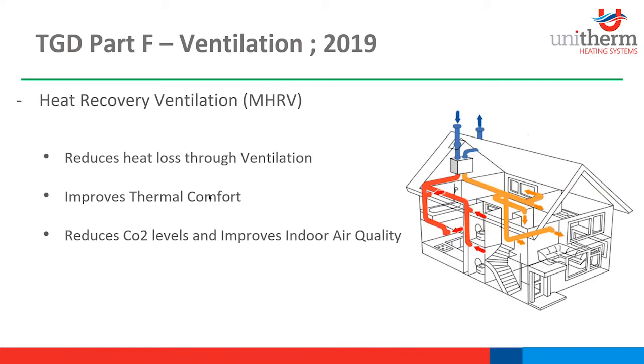So if you had warm air at 22, for example, and your cold air outside at 5, the supply air to your living rooms and bedrooms will be about 17, 18 degrees, depending on the efficiency of your heat exchanger. So you've no compromise there on thermal comfort, as fresh air is preheated through the heat exchanger before entering the envelope. And our systems as well, as I talked about, the humidity sensor and the DCV: our heat recovery systems here in Uni-Therm, our Blauberg systems, use humidity sensors to boost the fans when this set point relative humidity level is reached.